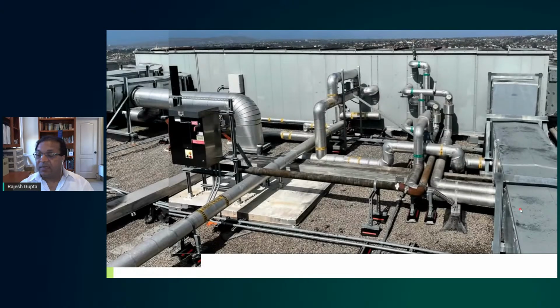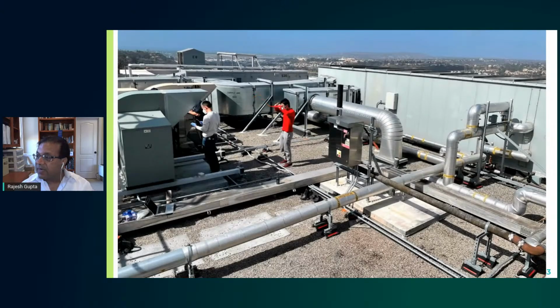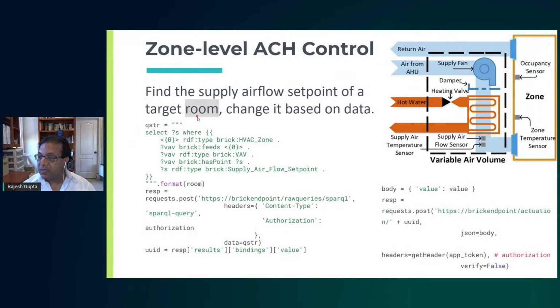This is another one, actually at a hospital where we have COVID patients. This is the return air here. This is the chilled water loop, and this is the hot water loop. There are filters here, and then your supply goes in there. You have 2 supply vents coming here, one going inside the building. Now you can see the challenge you run into. Your air is coming in, and that air has to be purified in this air handling system. You can monitor it here, see how good the quality is, and of course manage it against energy consumption and so on. This is my postdoc and students taking samples of the air for presence of the virus, and from the exhaust, unfortunately, we find quite a bit of virus in the exhaust.